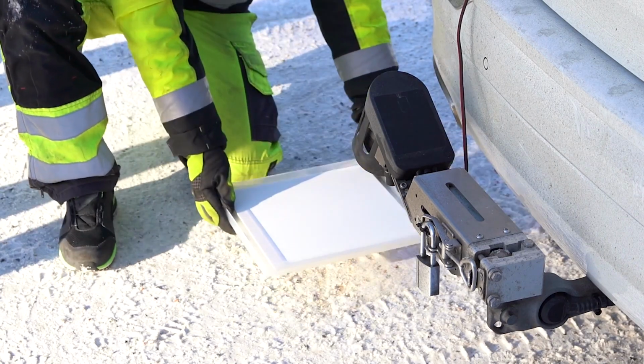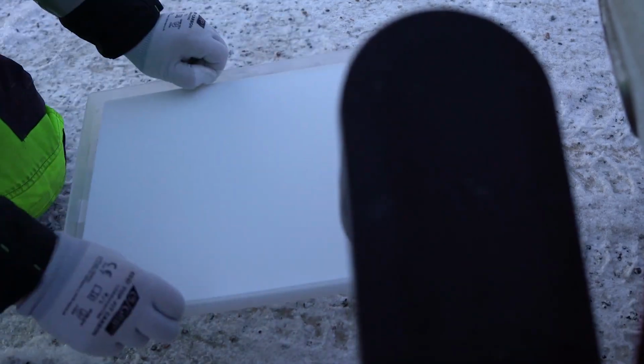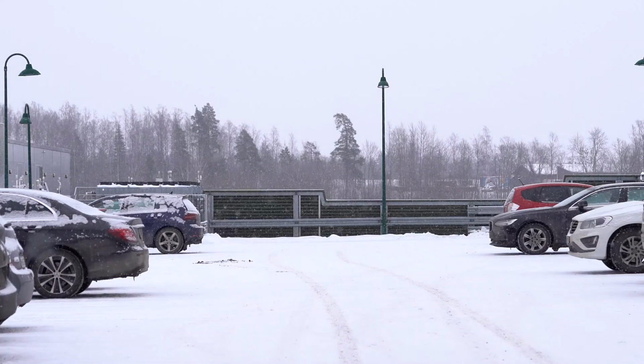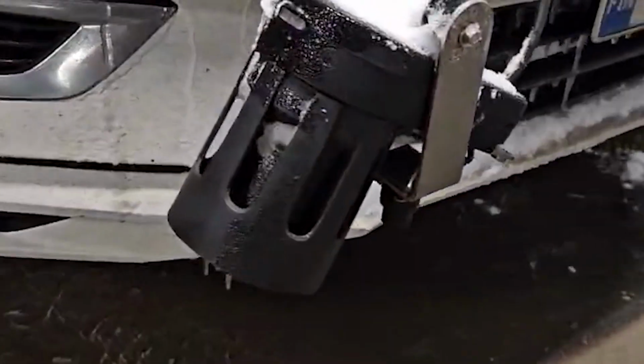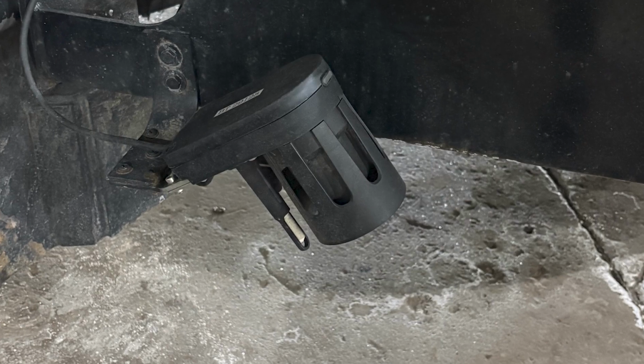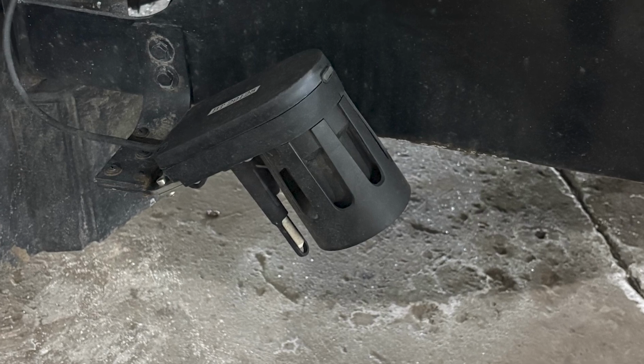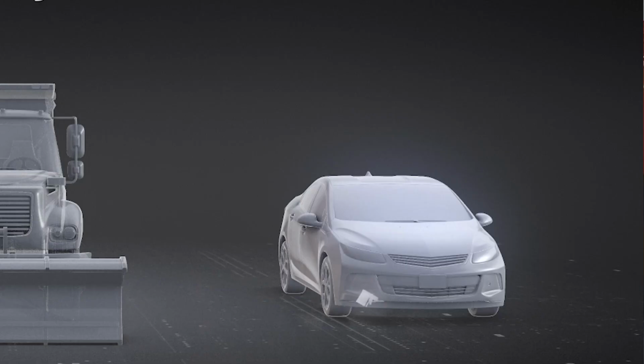Do not run calibration in direct sunlight, in fluorescent lamplight, or exposed to flashing lights. Do not run calibration in any precipitation or other conditions where the calibration plate may not be completely dry. It is mandatory to run plate reference calibration after every installation and adjustment of mounting.